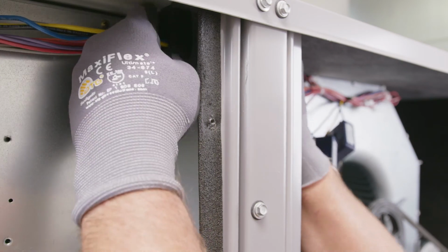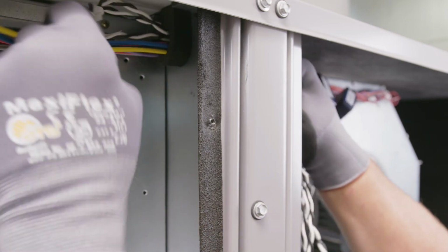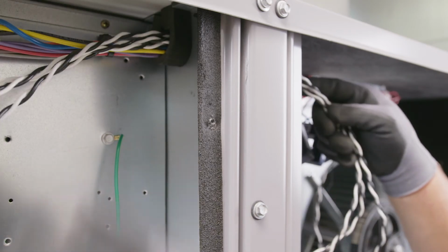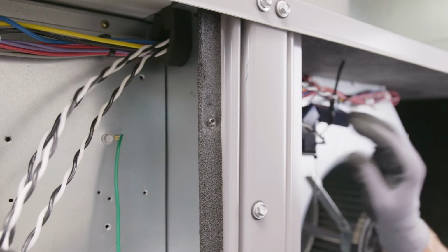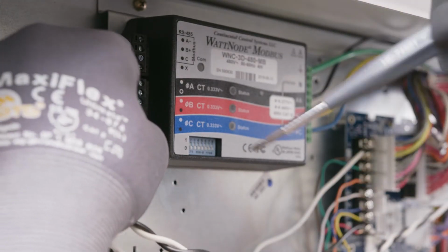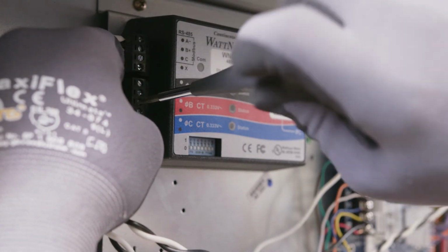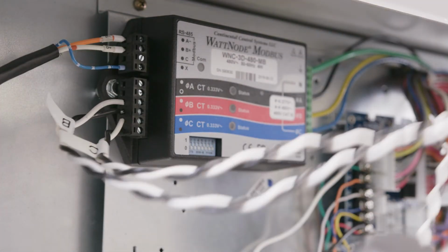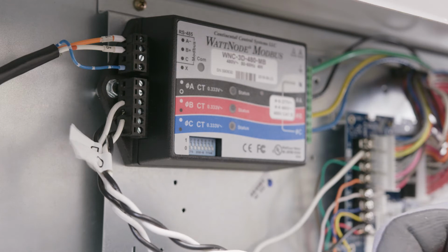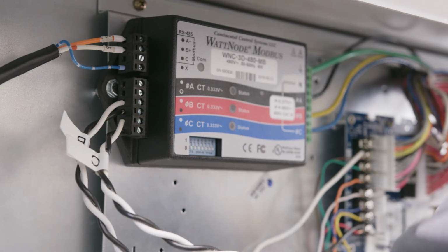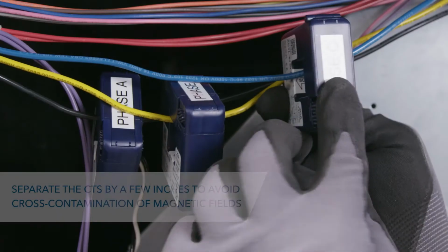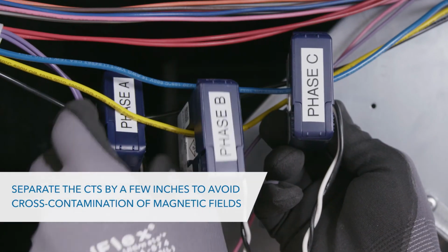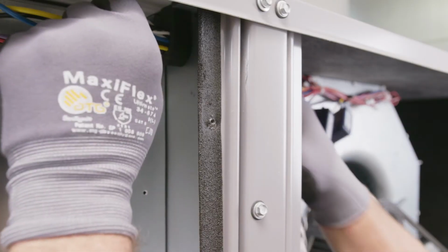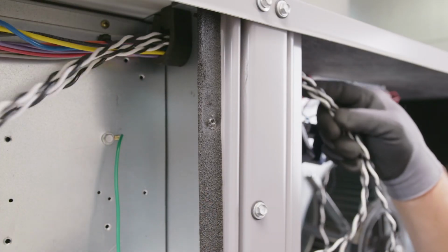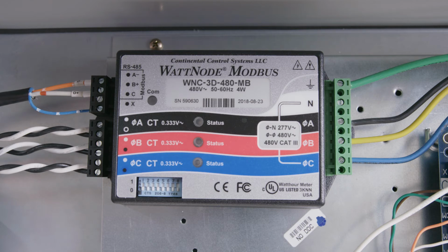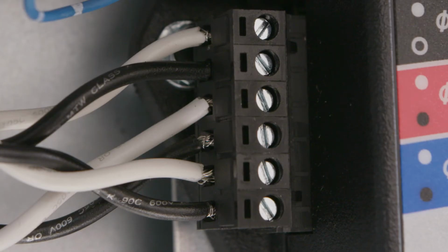The next step is to route the wires from the CTs over to the meter, which we mounted in the control panel. First, simply route the wires through the existing conduit channel for the unit. Then mount the first A phase CT on the power wire for phase A, which is the black on this unit. Again, making sure the arrow on the CT is pointing towards the power source of the unit. Repeat this step with the B and C phase CTs. Make a point to separate the CTs by a few inches, so you avoid cross-contamination of magnetic fields. Next, run the wire across the control panel to the power meter. Finally, connect it to the A, B, and C phase terminals. Again, white on top and black on the bottom.